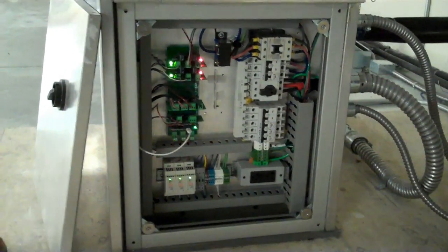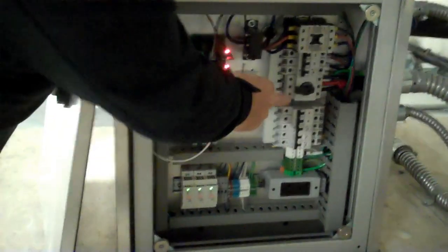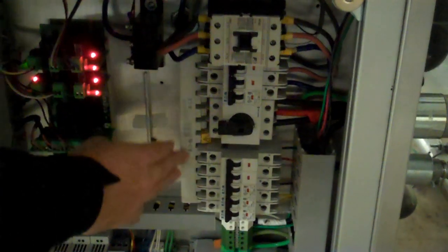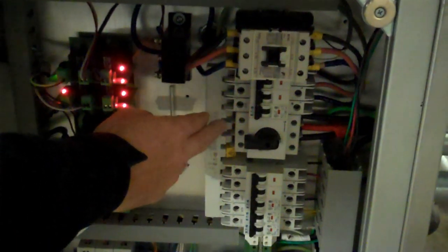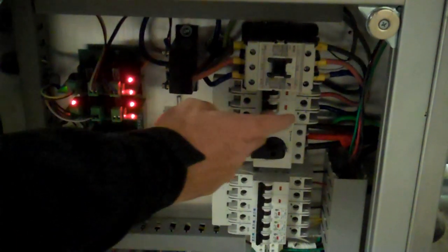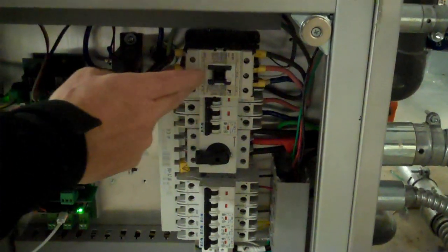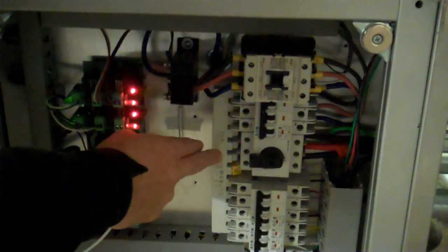Here the main power comes in to this disconnect right here. That feeds this three-phase bus bar. And the three-phase feeds this breaker, which feeds a contactor for the compressor. And then the breakers down here feed the cases. So you don't need other distribution panels around the supermarket.